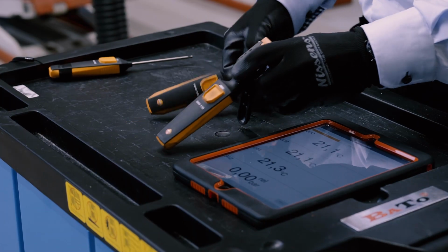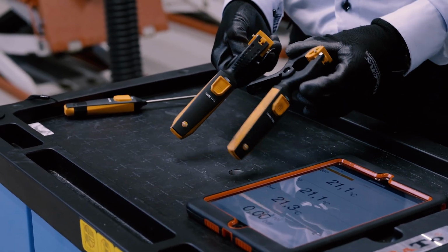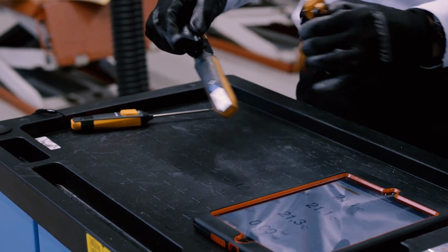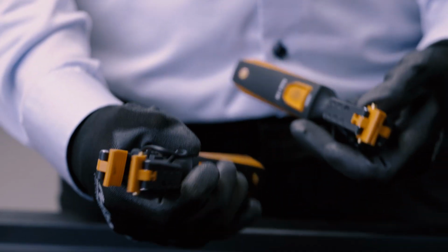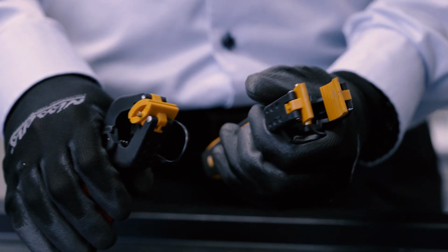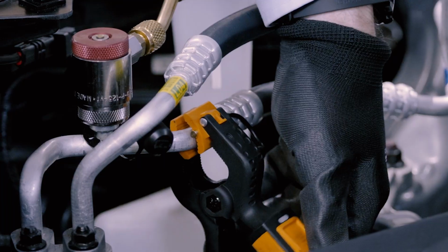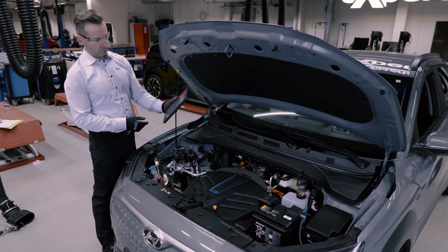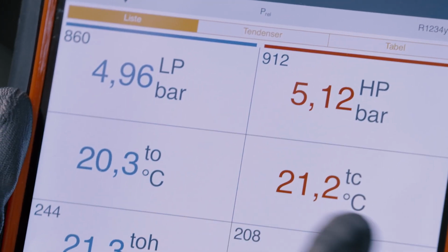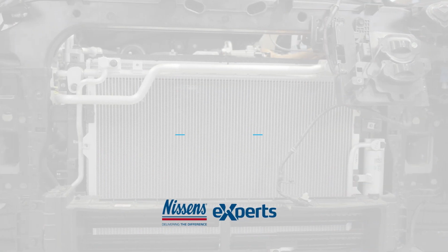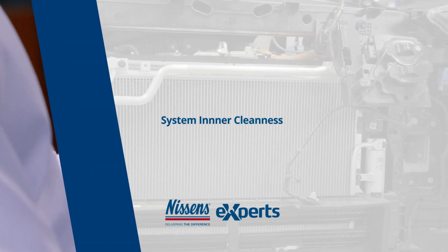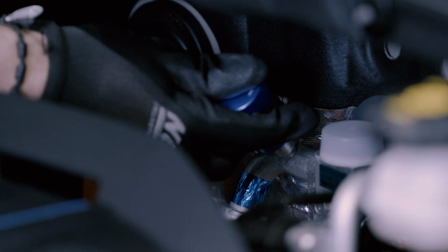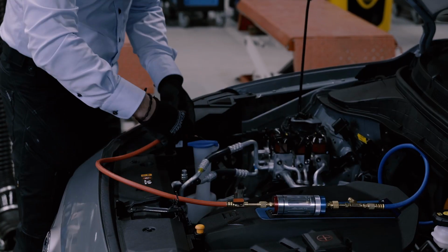The temperature-based diagnostics of the loop components is another vital test that can be carried out for the heat pump system. Excessive temperatures can be linked to severe failures, such as faulty or blocked valves or inner clogs in the heat exchangers. Temperature measurement on each side of the solenoid valve can reveal if it is fully closed or blocked. The system cleanness inspection is another initial and highly recommended troubleshooting.